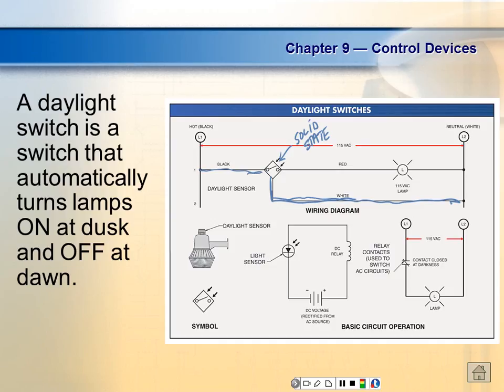One of the problems we have is most solid state limit switches only have 1 or 2 contacts. Some only have 1. I didn't say always like the book says, I said usually. With these devices, they usually only have 1 contact, but that's no big deal because we can use that 1 contact to bring in a control relay. That control relay can have a lot of normally open and normally closed contacts. I think ours has 3 normally open and 3 normally closed.